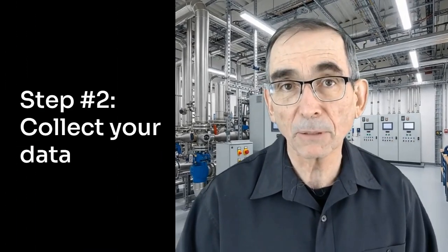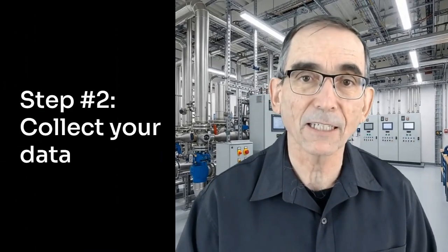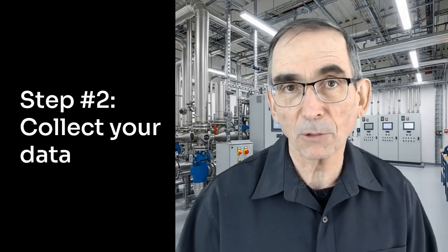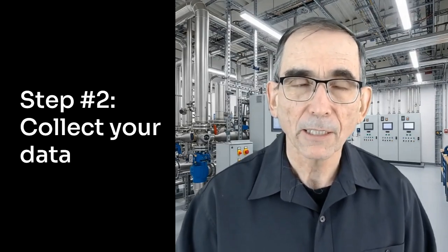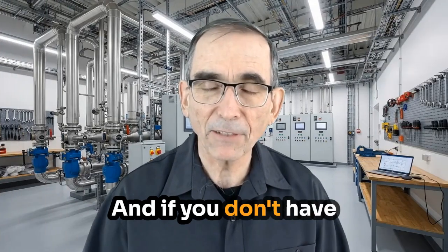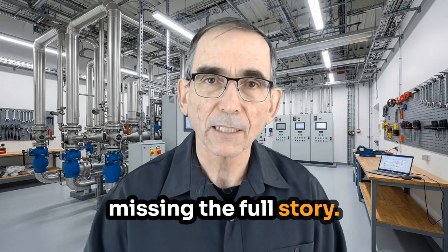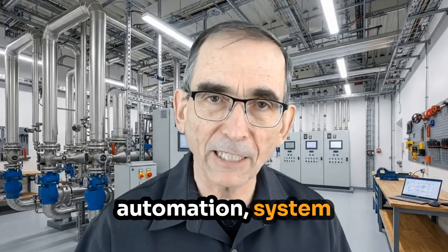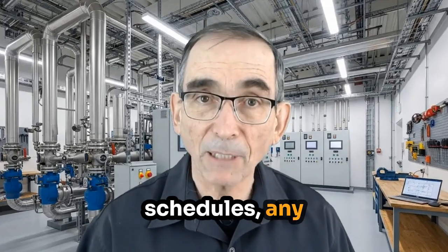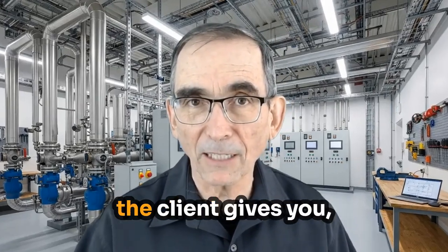Step two is to collect your data, but before you even set foot on site. You want at least 12 to 24 months, preferably 24 months of utility bills. And you need to get interval data. And if you don't have that data, you're really missing the full story. Ask for building automation system exports, equipment schedules, any past audit reports. According to ASHRAE, audits with 12 plus months of data are 40% more likely to identify actionable savings. So don't just take what the client gives you. Ask for what you need. If the data's a mess, that tells you something about the site's operational discipline.